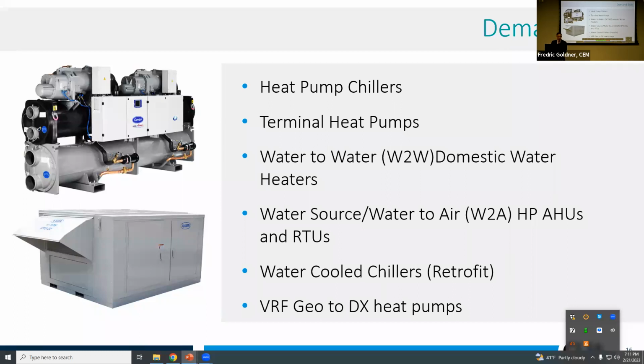And the concept is that rather than having to have these chillers, because most buildings have the core, which always needs air conditioning, and then the perimeter loop, which may need heating or cooling depending upon the season. These were invented so that we could basically wrench the heat off of our core and then immediately put it in the perimeter without sending it back to your plant, without having to pump that energy back down to the plant and convert it over to the other side. So yeah, you don't have to buy that chilled water. You don't need a chiller anymore.